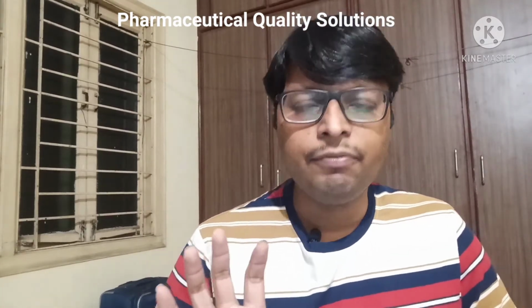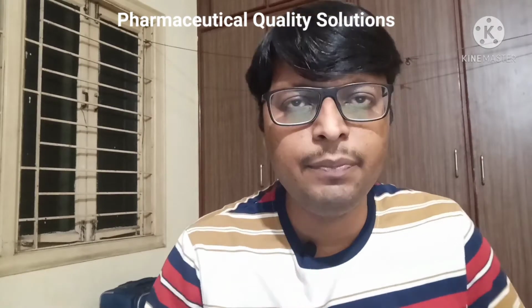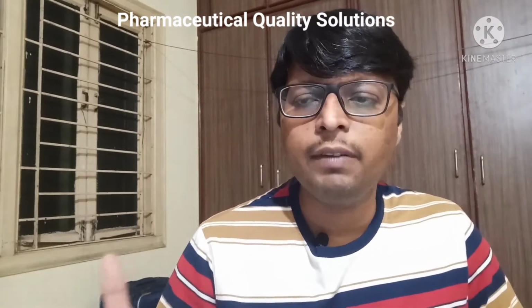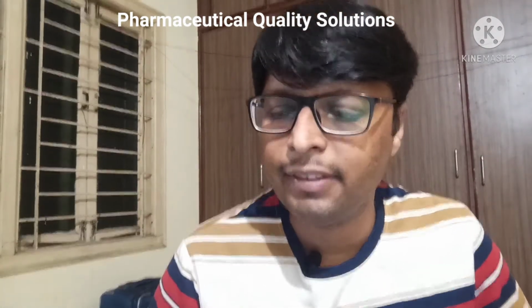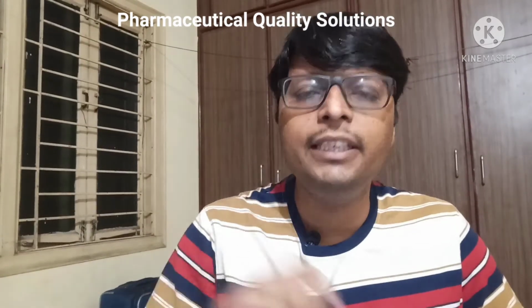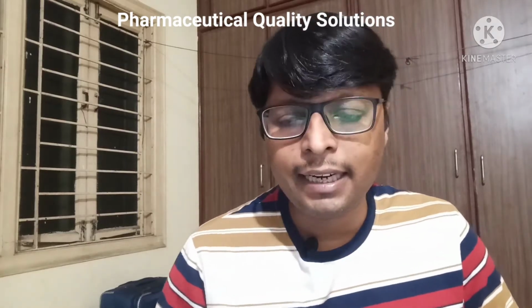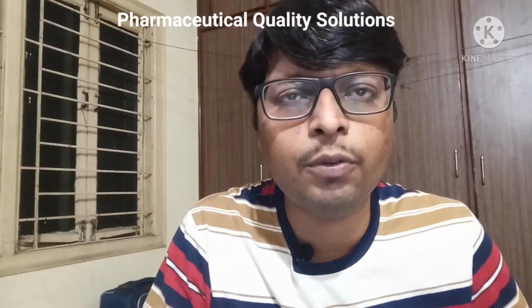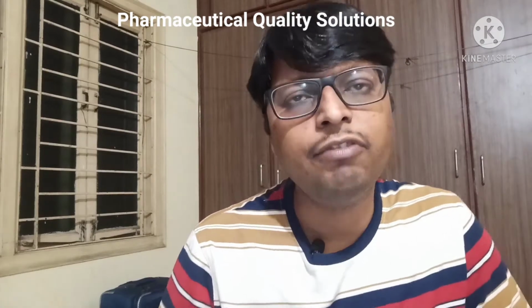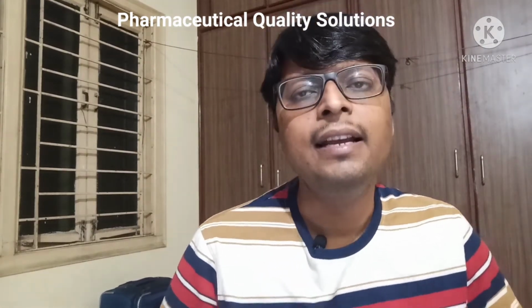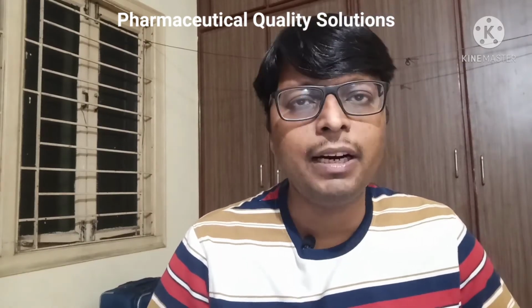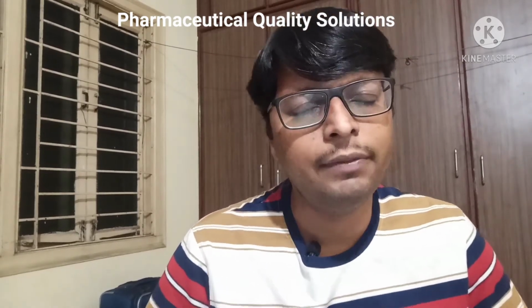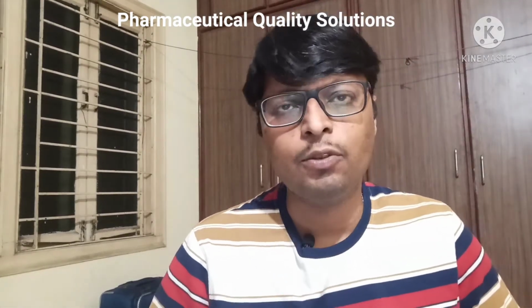Suppose you purchased a pH meter and you have a known buffer solution of pH 7. You check how much the instrument is showing, since 7 pH should read 7. So you are checking whether the instrument you purchased works properly accordingly; that is performance qualification. Some people also say calibration is part of the PQ, performance qualification, so you can say calibration is also performance qualification.